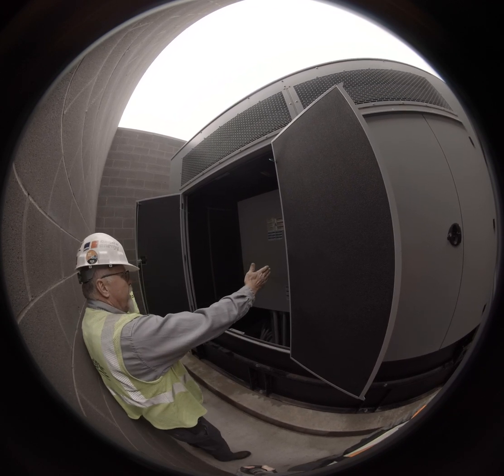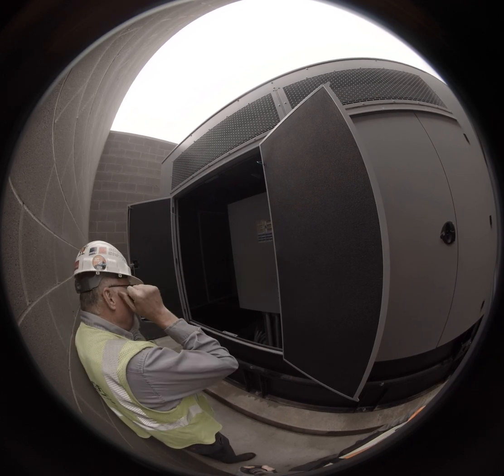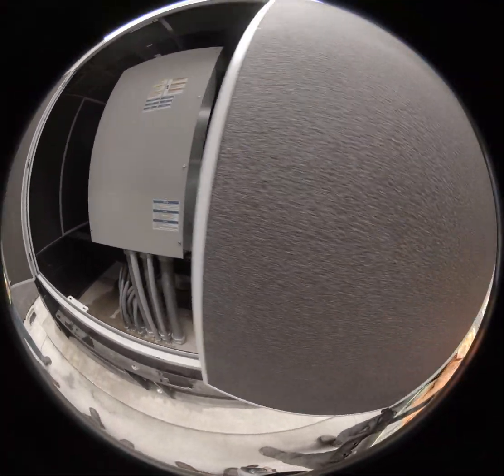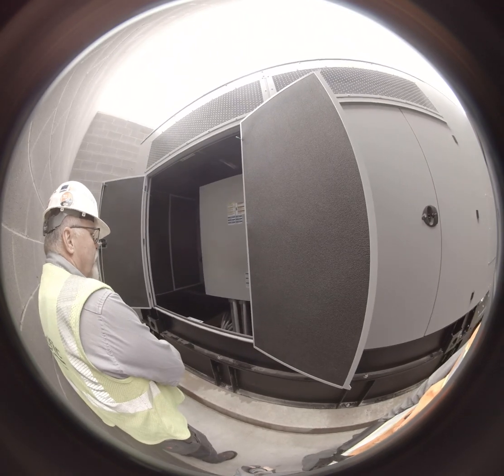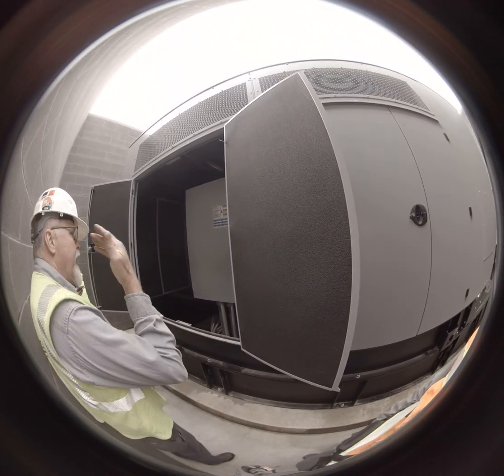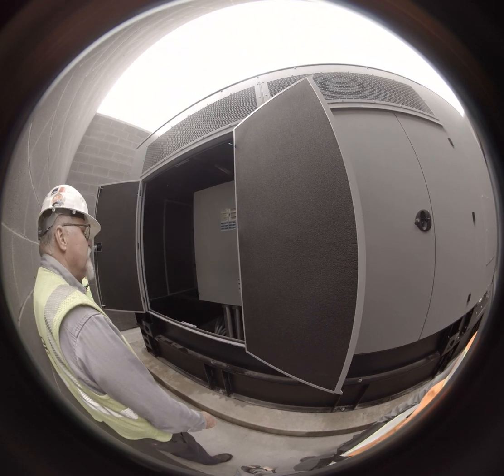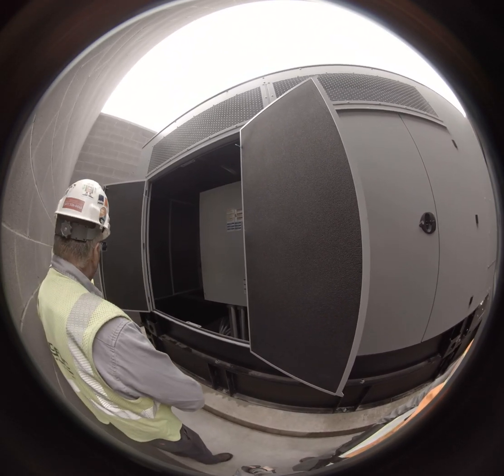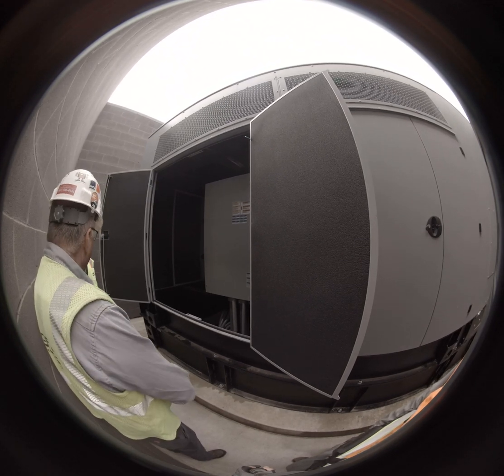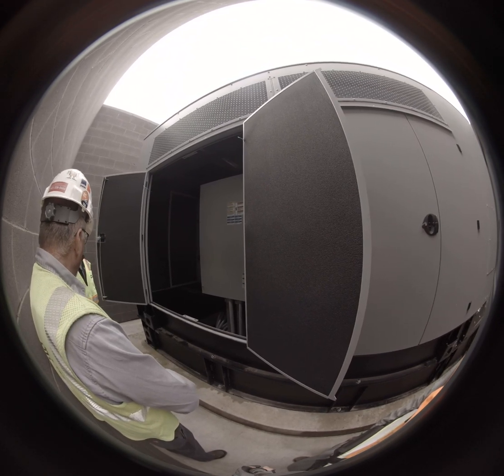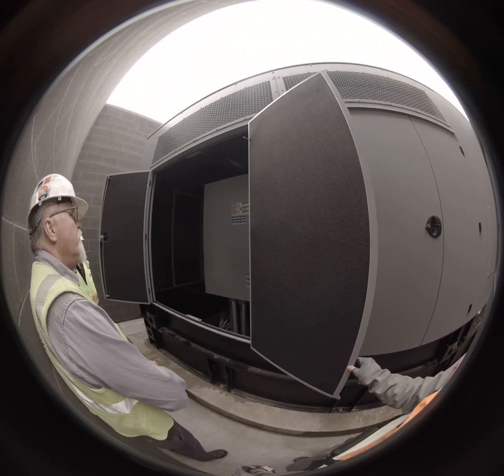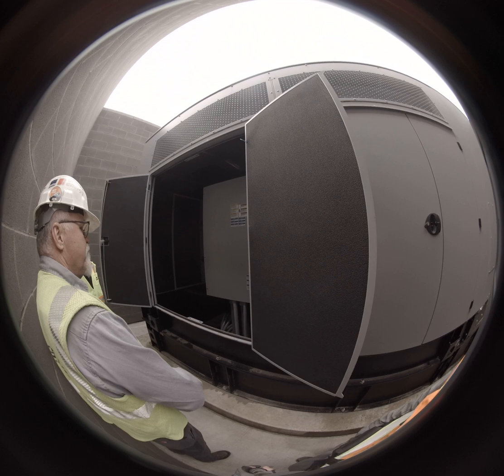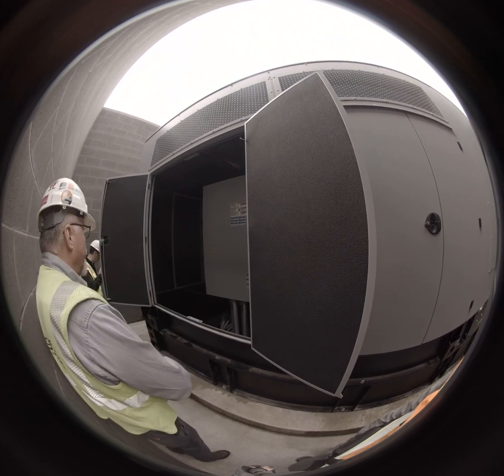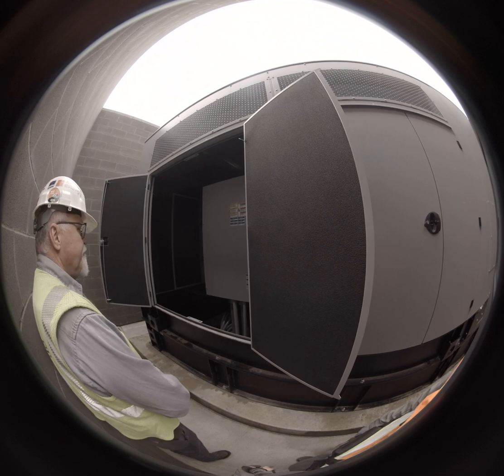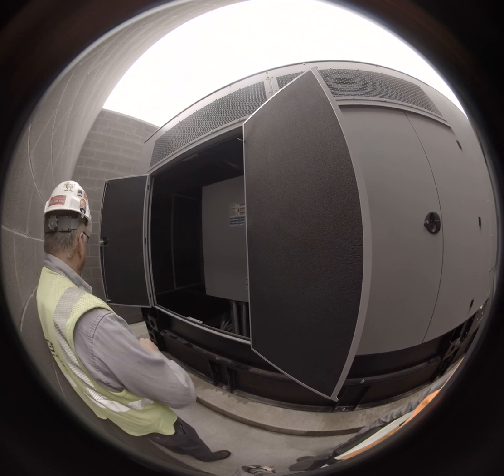Right over just in front on top of the winding, you're going to see the data tags up there. The data tags are from MTU Onsite, Rolls-Royce, and Marathon on this particular set of tags. The MTU Onsite, you can use those numbers and order any part you want off of this machine that was supplied by MTU Onsite Energy / Rolls-Royce Power Systems. If you wanted to go elsewhere and say you want a new voltage regulator, you can go through the Marathon side, or a bearing for it, or whatever on it.